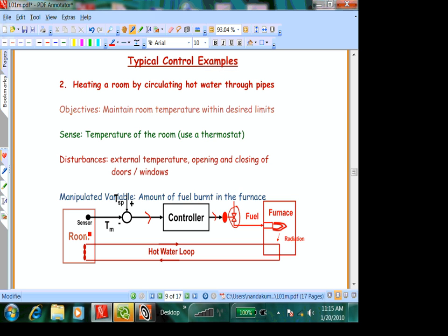So you are measuring the current patterns and using a model, knowing what the difference is, predicting what the required duty is, and sending it back. Now if you wait a few minutes, you'll find the error goes down. When the error goes down and the set point is the same as the measured temperature, the signal is smaller, and that means it shuts off. So it's putting together, integrating what happens in the process.